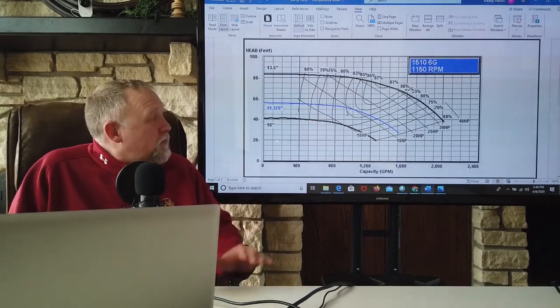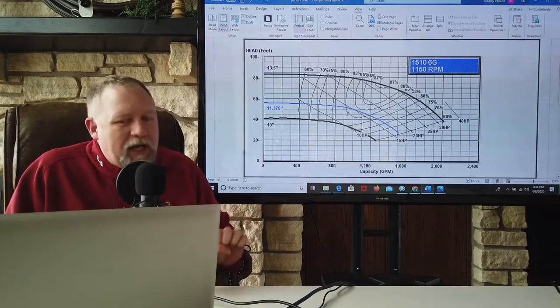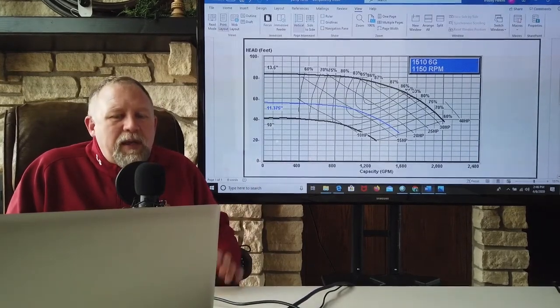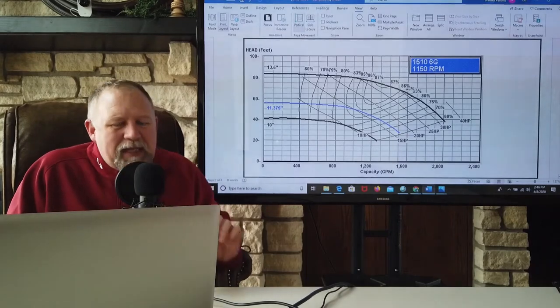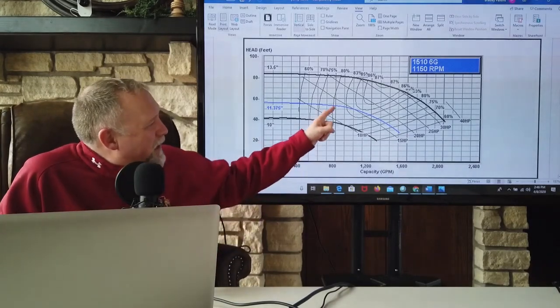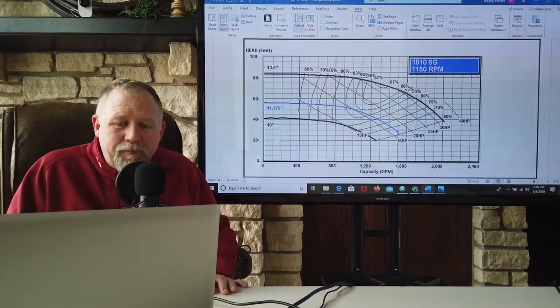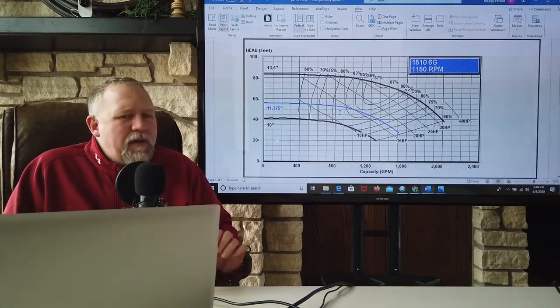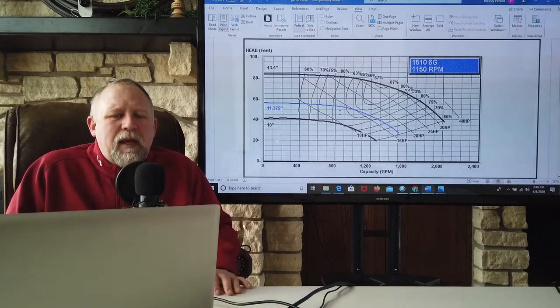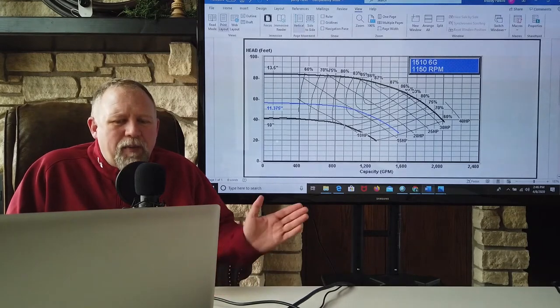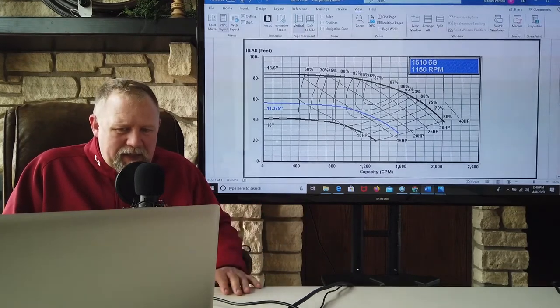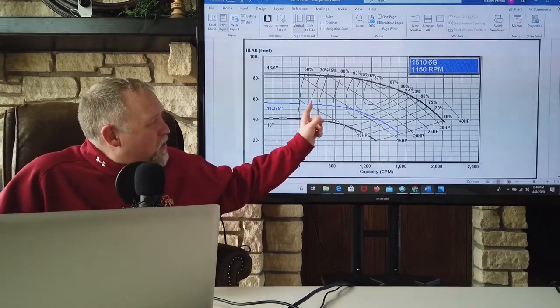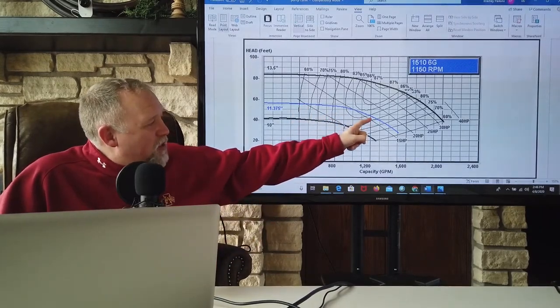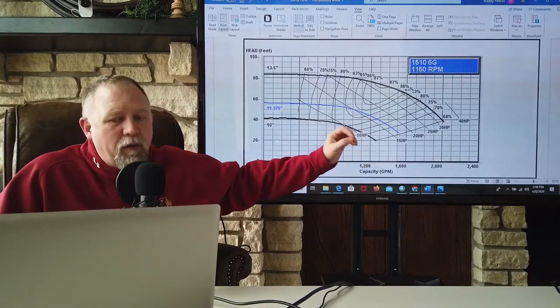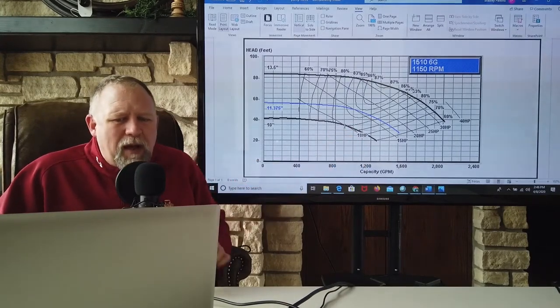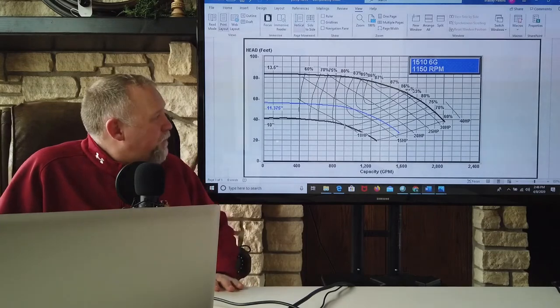You might say, well, let's put a 15 horsepower motor on because it would work for this particular impeller at this particular duty point. That is correct, it would. However, if something was to happen and that pump started operating at a higher flow rate, then it could potentially move this way on the curve and actually overload, and that's what we would call an overloading pump curve. Well, how could that happen? Let's just give an example.